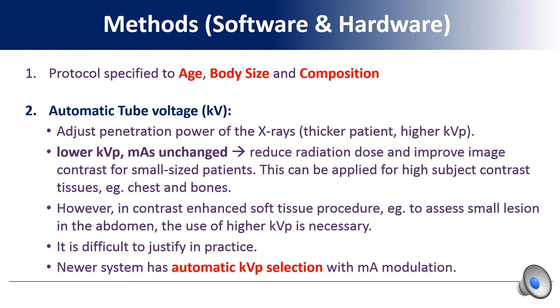Taking the first example of automatic tube voltage, kVp adjustment, we know that adjusting the kVp will adjust the penetration power of the X-rays. As a general rule, for thicker patients, we use higher kVp. However, if you lower the kVp and the mAs remain unchanged, it could reduce radiation dose and improve image contrast for small-sized patients. This can be applied for high-contrast tissues such as the chest and bones. However, in contrast-enhanced soft tissue procedures, such as to assess small lesions in the abdomen, the use of higher kVp is necessary. It is difficult to justify in practice. Therefore, modern systems have what is called automatic kVp selection with mA modulation functions.